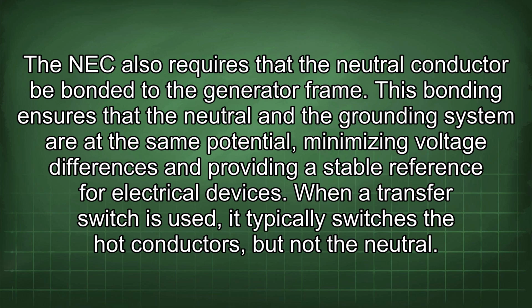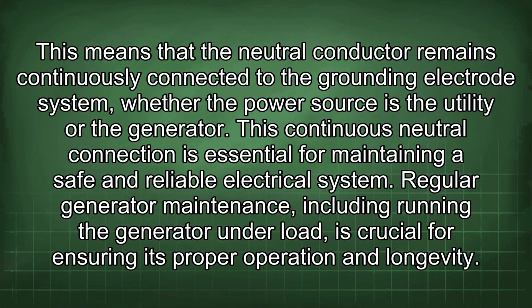When a transfer switch is used, it typically switches the hot conductors but not the neutral. This means that the neutral conductor remains continuously connected to the grounding electrode system, whether the power source is the utility or the generator. This continuous neutral connection is essential for maintaining a safe and reliable electrical system.